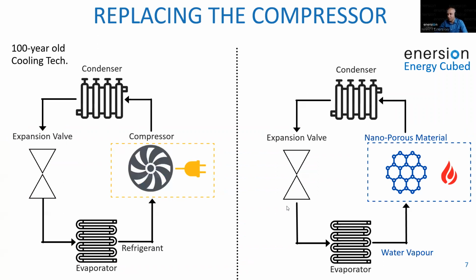For those who want to know more, here is an abstract thermodynamic cycle comparing both technologies. On the left-hand side is a traditional air conditioning system or heat pump. You have an evaporator, a synthesized refrigerant in the loop, and a mechanical compressor connected to the grid that uses grid electricity. The refrigerant evaporates from the evaporator, giving you cooling, and then the compressor pushes the evaporated vapor into the condenser, and the cycle continues. That was the cycle originally introduced for all heat pumps and air conditioning systems.